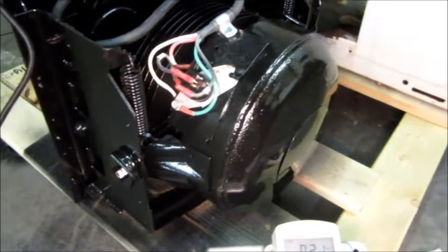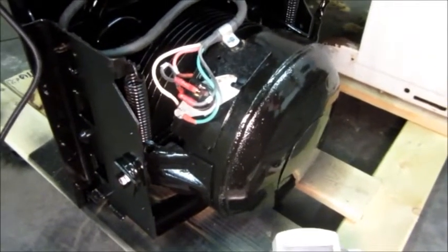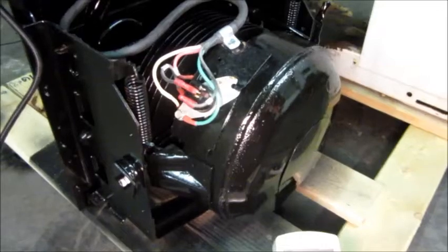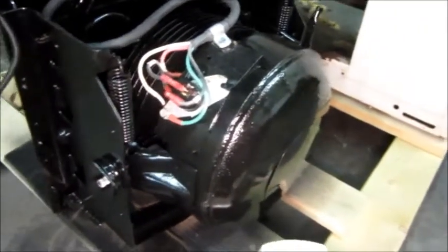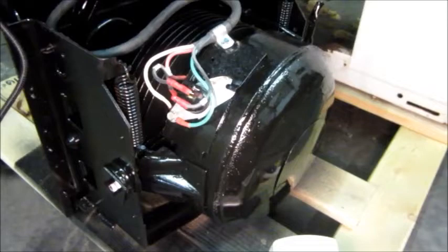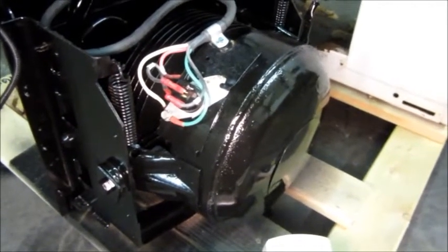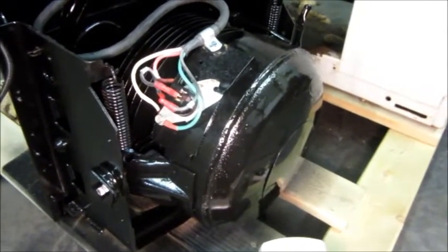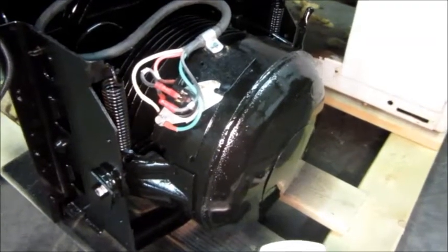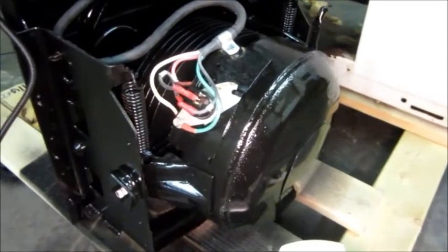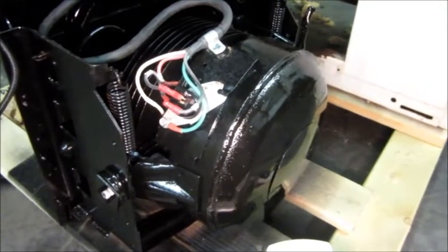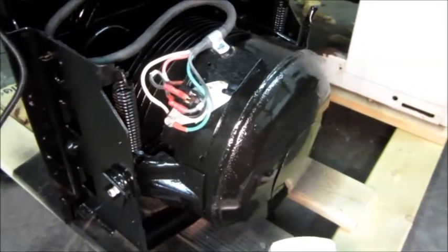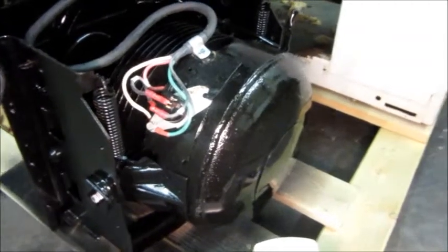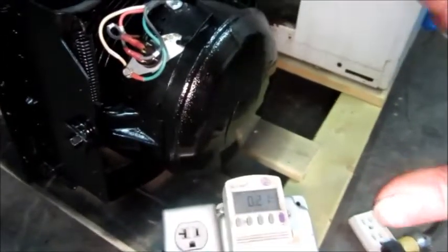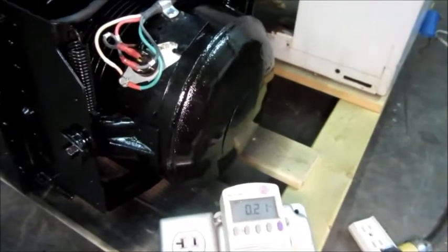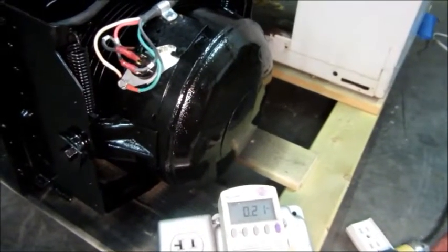Now it ought to sit here and wait for several moments. And then once the circuit breaker's cooled off, it'll make another start attempt by itself. This is what would happen if there were a power blink and the power went off and came right back on, or if someone turned the control off and right back on. But you have to be sure that that function is working. It may seem stressful and people don't like to see this, but it's got to be tested, because I can intervene and turn this off on the switch if I think it's not tripping like it should. But if I send it on home and I haven't tested it, then it could be a disaster.